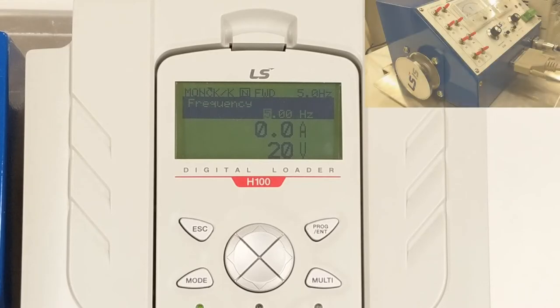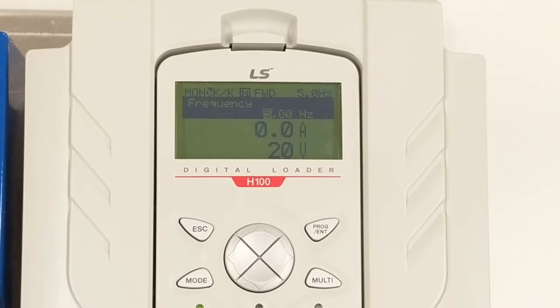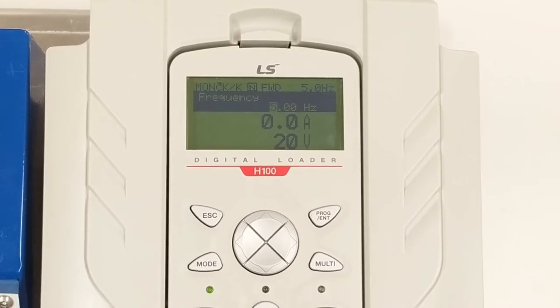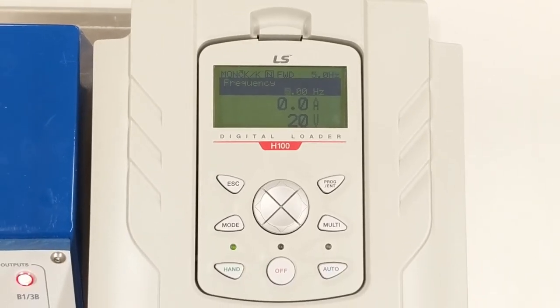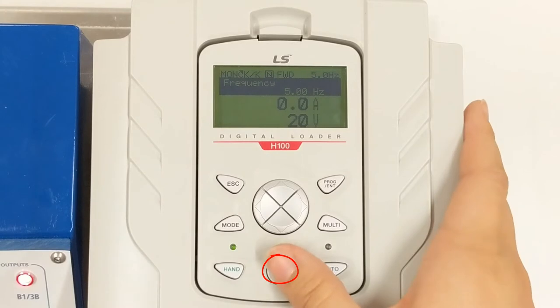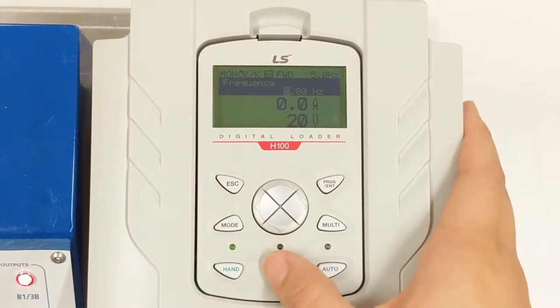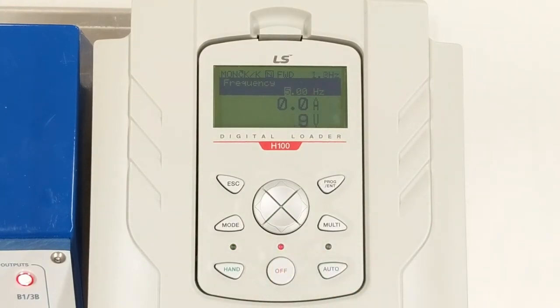Check your motor direction. If the motor direction is backward, power down the VFD and swap any 2 motor leads on the output of the VFD. Perform the same hand operation test again to verify direction is correct. To stop operation, simply press the off key. Notice that you will see your output speed in the top right corner decrease as the VFD decelerates.